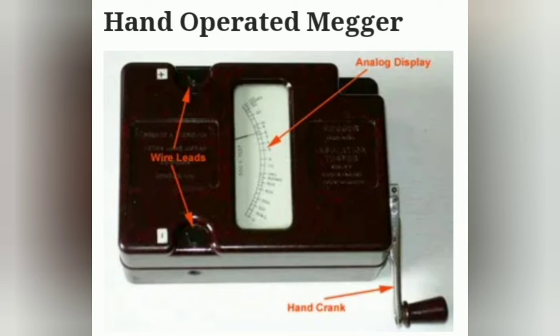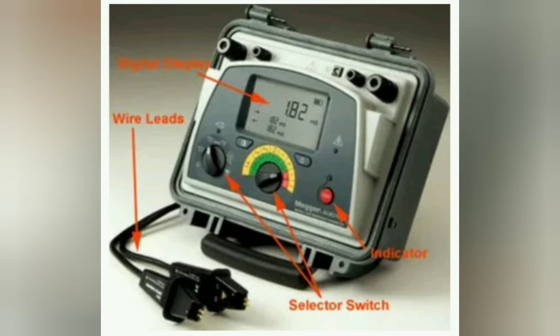There are two types of Megger Tester: manual type or hand-operated, and electronic type or battery-operated. The parts are wire leads, selection switches, and indicators. A digital display shows the IR value. Wire leads: two wire leads for connecting the Megger with the external electrical system to be tested. The selection switches are the switches used to select electrical parameter ranges. The indicator shows various parameter statuses, for example, power, hold, and warning.